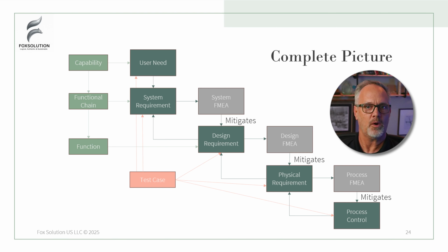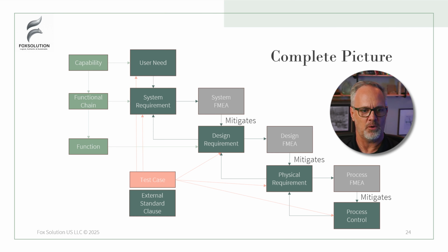So how are we going to assure that these are met? What test are we going to run? What's the procedure for the test? We have traceability to those external standard clauses. So we have an industry view of everything that's needed for the different scope issues inside of development of the project, whether it's 60601 or sterilization procedures or device specific stuff, testing procedures. All of the industry understanding has been baked into the requirements model.